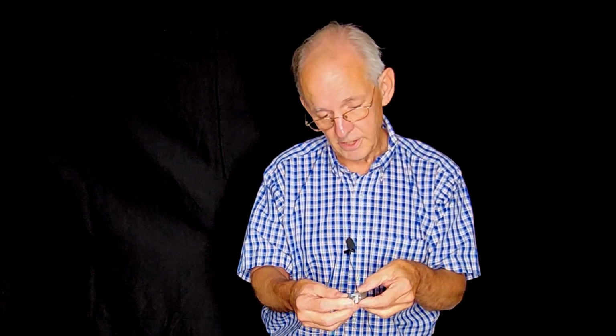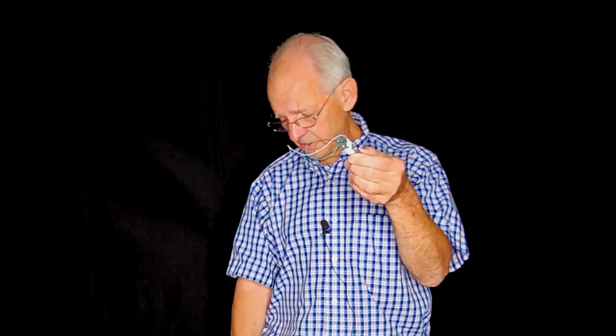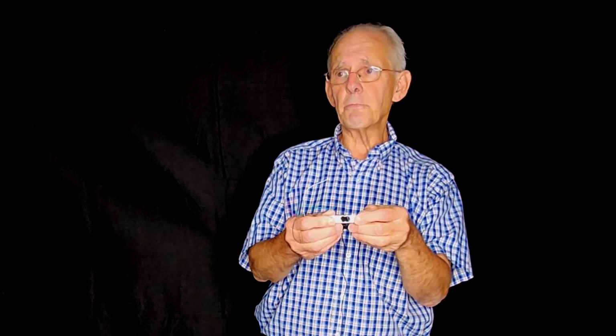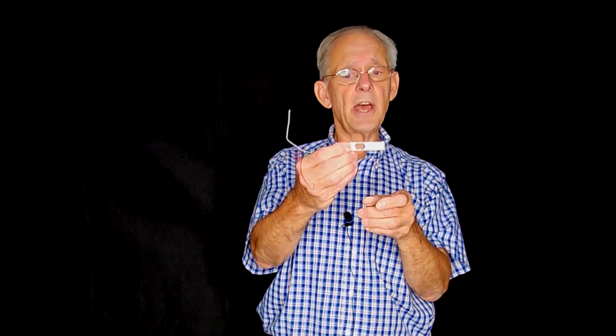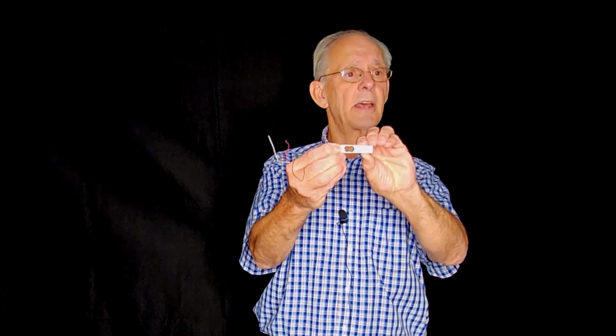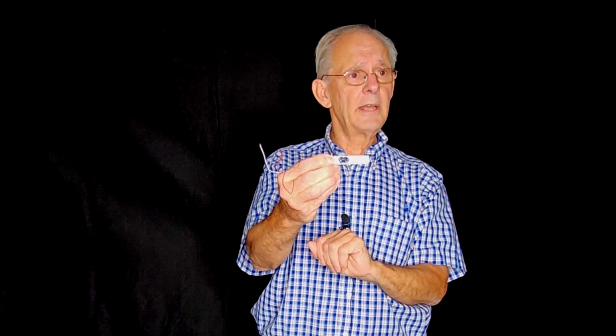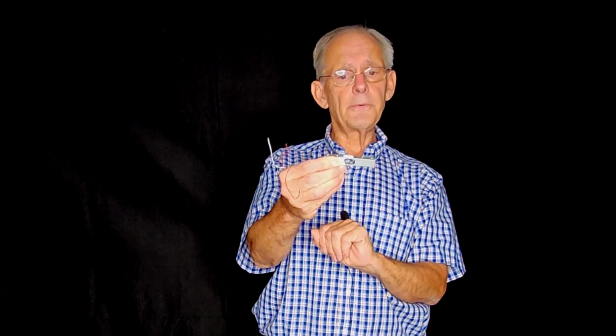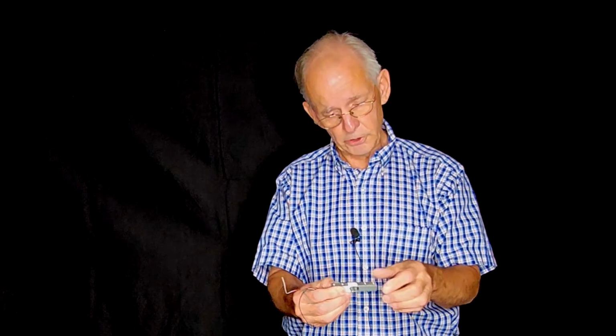Now, this one happens to be 1 kilogram. So that one's 5,000 kilograms. This one is just 1 kilogram. And we have one in a device we just built, which is just 100 grams. They all put the exact same output out. And this gives you force measurement. So you can tell how much pressure you're putting on something or what something weighs. And if you see most of the common electronic scales today, this is what's inside. One side is mounted and the other side has the pan on it. And that's how the scales work. So it's a very, very simple and very robust technology that puts out an analog signal.